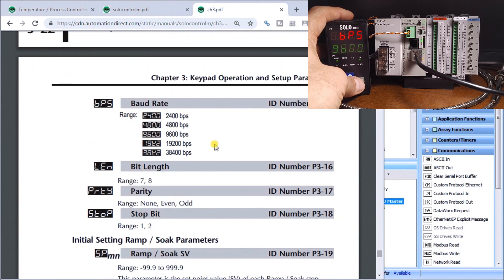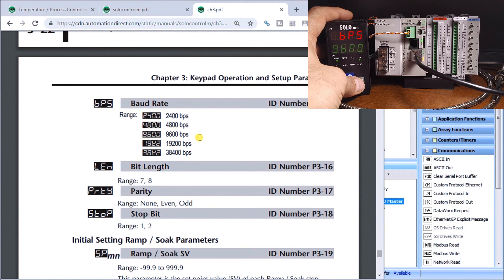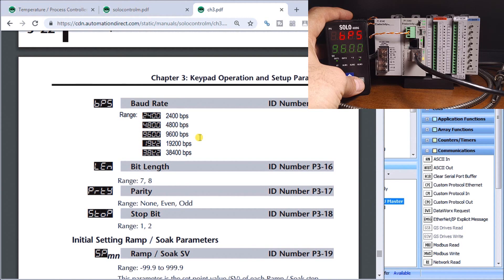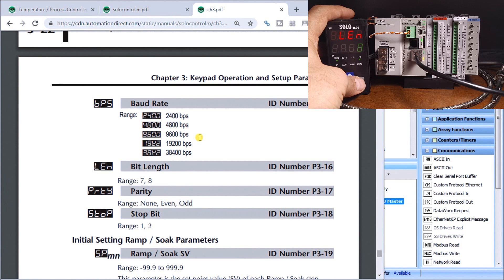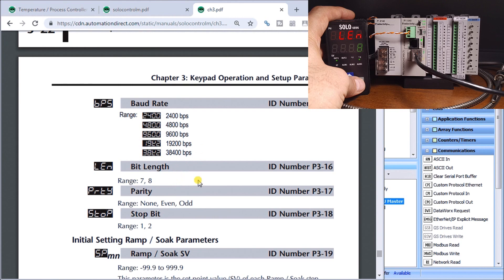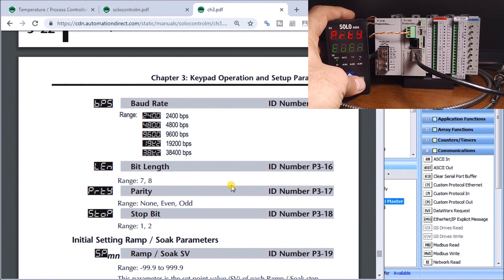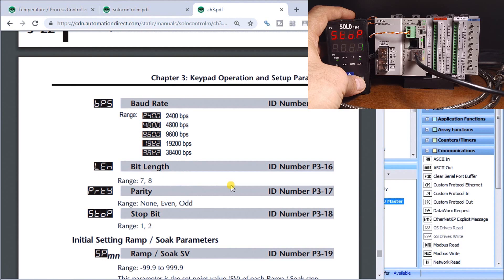Then we have our communication baud rate 9600, this is bits per second, the transfer rate between the solo and the productivity 1000 series PLC. This is length eight data bits and then we have parity which is set for even. Once more we have our stop bit which is set for one.